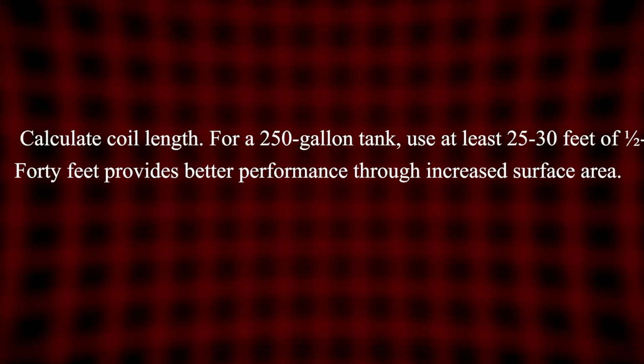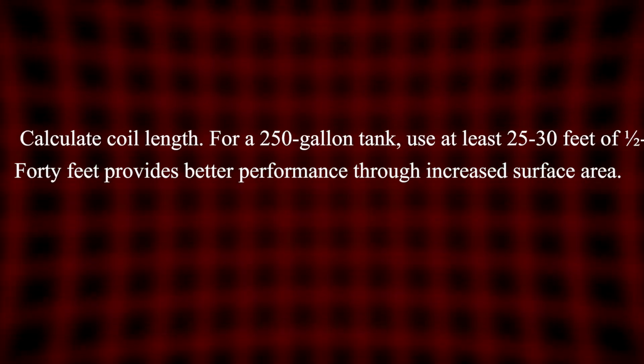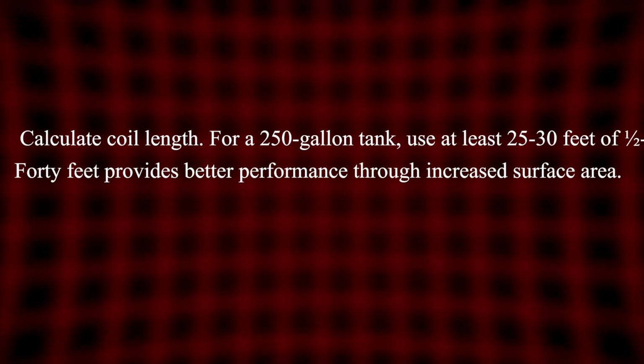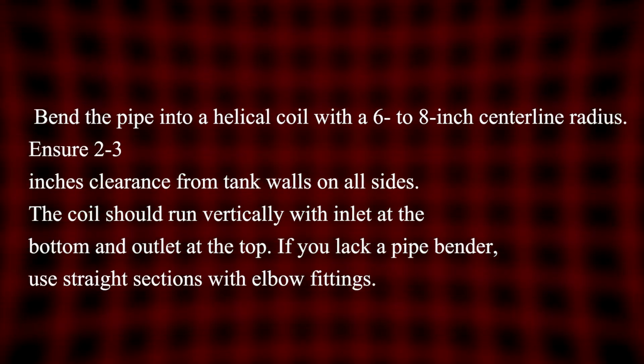Step 1. Calculate coil length. For a 250-gallon tank, use at least 25 to 30 feet of 1/2 inch pipe. 40 feet provides better performance through increased surface area. Step 2. Bend the pipe into a helical coil with a 6 to 8 inch centerline radius.